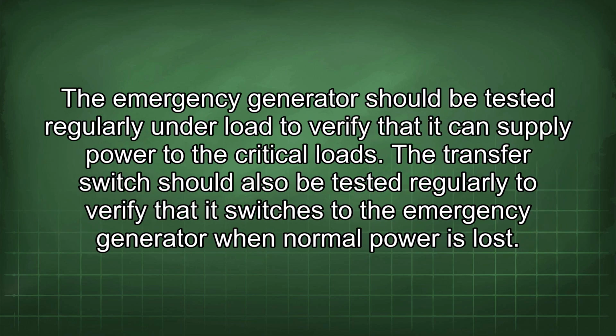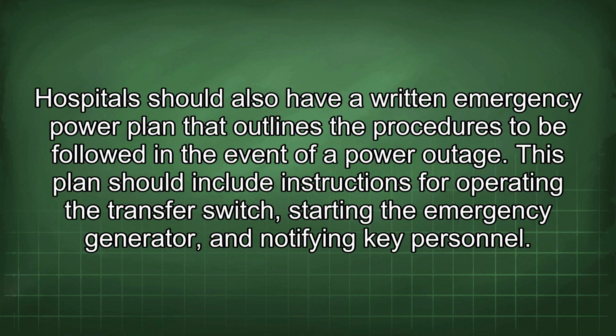The emergency generator should be tested regularly under a load to verify that it can supply power to the critical loads. The transfer switch should also be tested regularly to verify that it switches to the emergency generator when normal power is lost. Hospitals should also have a written emergency power plan that outlines the procedures to be followed in the event of a power outage.